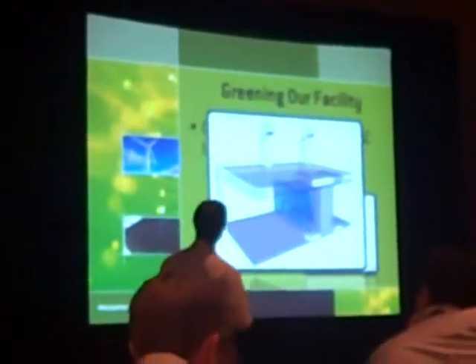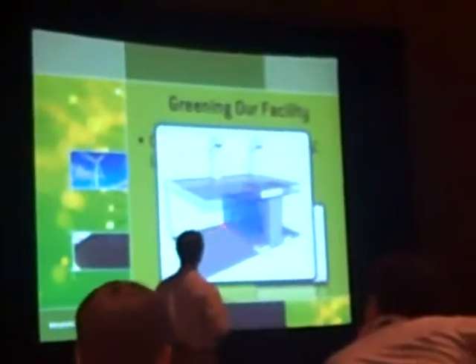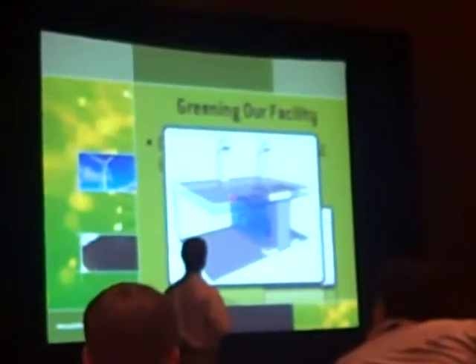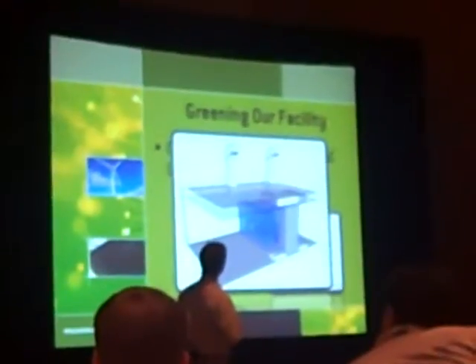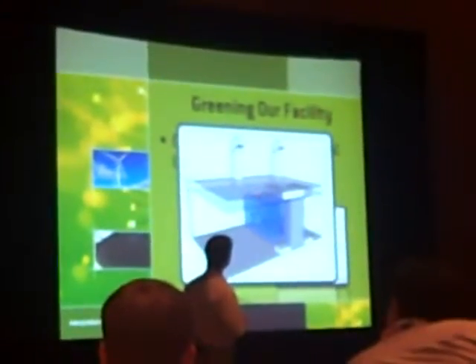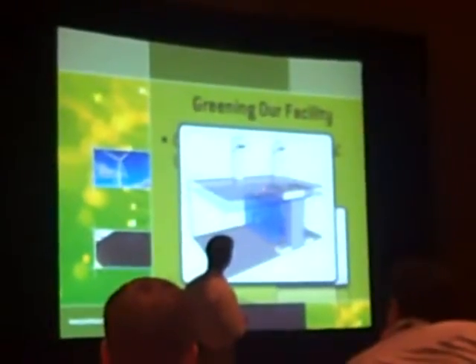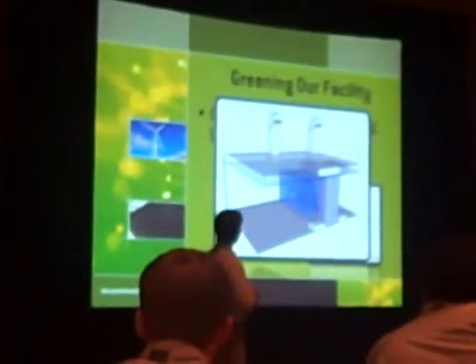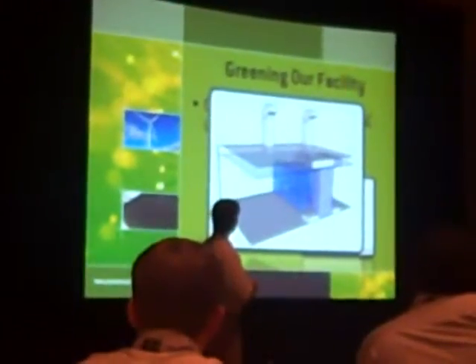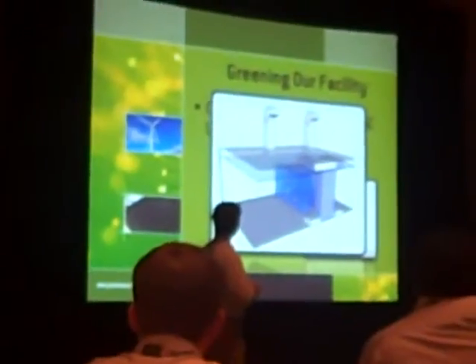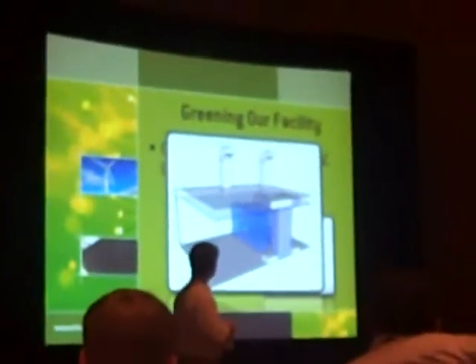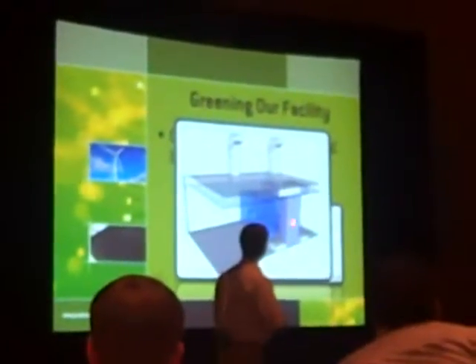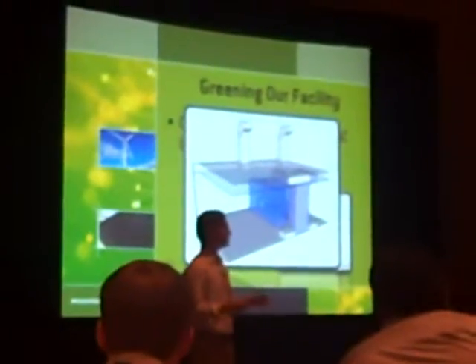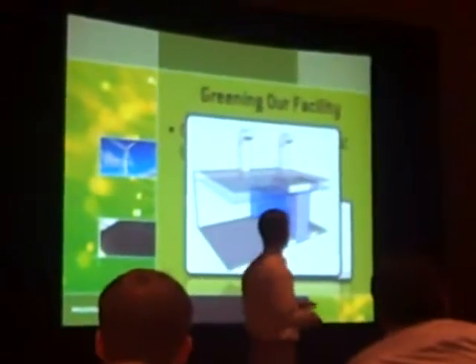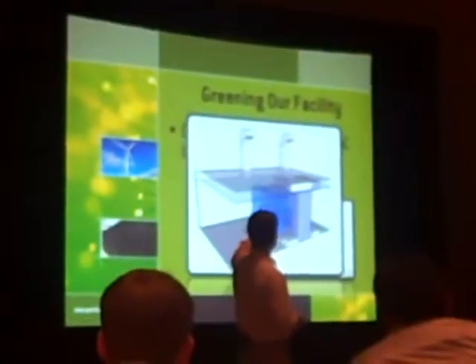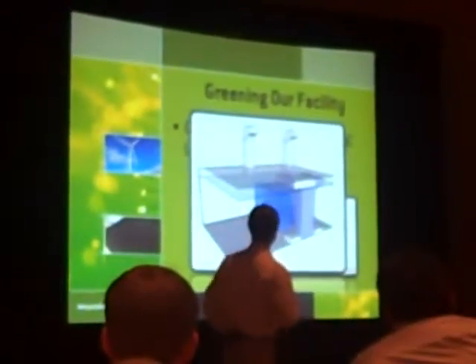So to kind of give you an idea, sorry for the childlike drawing here, I'm not very good at these 3D drawings, but out here, the Coolerados are pulling the air in, pulling it up into this plenum and then dropping the cold air in between our quote-unquote cold aisle, which is this aisle here. At the other end of our room, we have a CRAC unit, which basically delivers us 2N capabilities for cooling. It matches the capability of the cooling from the exterior.